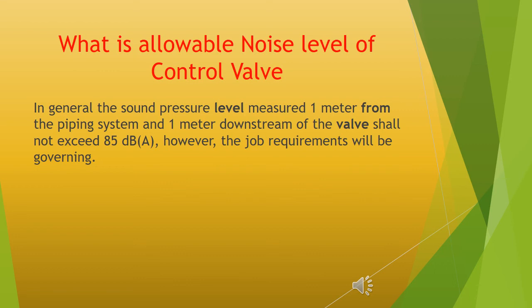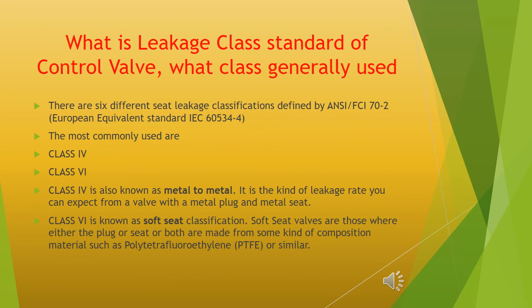What is the leakage class standard of a control valve, and which class is generally used? There are six different seat leakage classifications defined by ANSI FCI 70-2; the European equivalent standard is IEC 60534-4. The most commonly used are Class 4 and Class 6. Class 4 is also known as metal-to-metal — it is the kind of leakage rate expected from a valve with a metal plug and metal seat. Class 6 is known as soft seat classification; soft seat valves are those where either the plug, seat, or both are made from a composition material such as PTFE or similar.